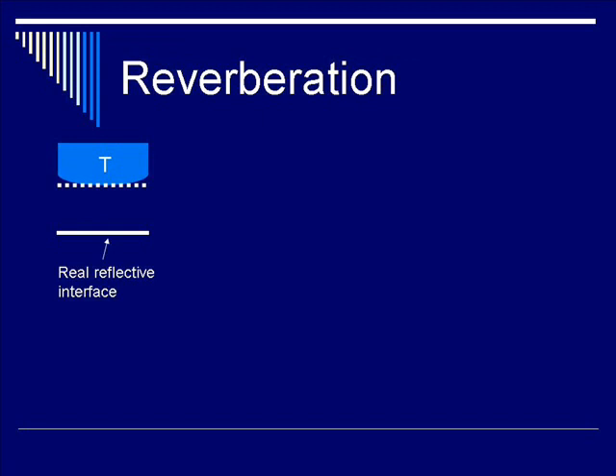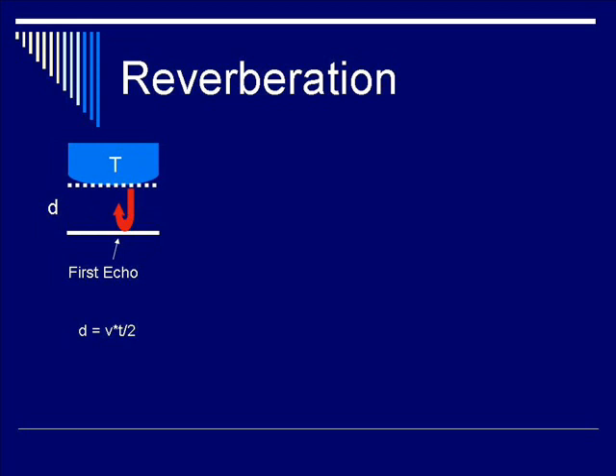How does this work? Looking at the illustration, you have a transducer labeled T with the surface marked by a dotted line. Ultrasound waves emanate as pulses from the machine towards a highly reflective surface or interface, which reflects the ultrasound wave back towards the transducer. This reflective echo gives you the signal to form the image on the ultrasound screen. The red arrow denotes the signal returning from the interface — the first echo and the real image — at distance d from the transducer surface, calculated by the equation: velocity times time divided by 2.